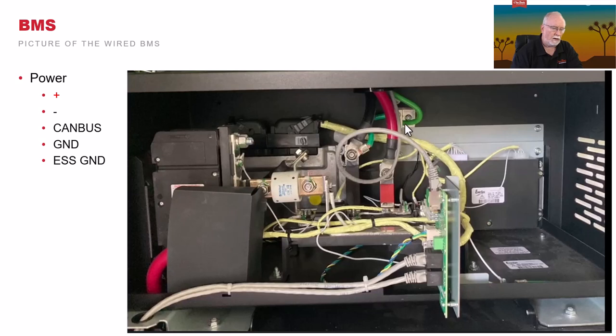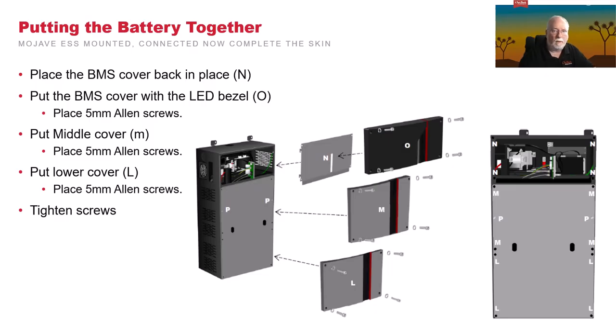As you notice, it can go through either side of this connector. So in my case, it was easier to do it from that side. And then finally, I have the extra wire looped around, but this is my CAN bus connection. So effectively, again, positives connected, torqued. Negative connected, torqued. Grounds are all made as needed, and the CAN bus connection is made. What you do not want to do in this system is unplug, disconnect, or modify any of the other connections in here. The next step in the battery assembly is to put the covers back on.